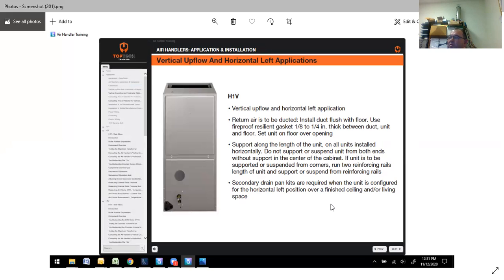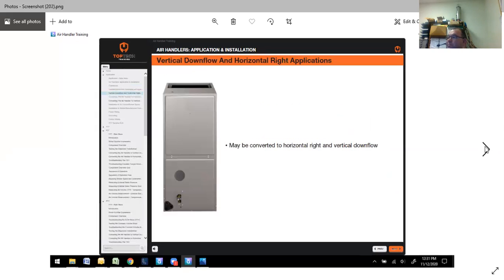secondary drain pan kits are required when the unit is configured for horizontal left position, really any position, if you're going to be over a finished ceiling or living space. Normally it's not a matter of if it's going to leak, it's a matter of when it's going to leak. You do not want to have a ceiling come down. I've seen too many of them do that: somebody not putting pans in, not wiring the safeties up correctly, not wiring up safety at all, and then they're looking at replacing a whole ceiling or worse. These may be converted to horizontal right and vertical downflow.